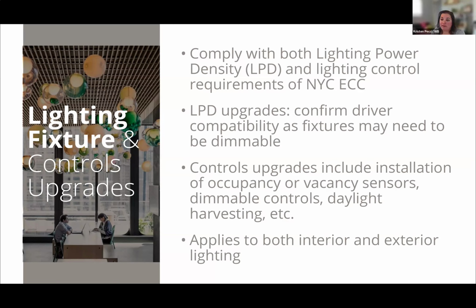The second part of the lighting upgrade requirements does factor into the control side, and this would include installation of automatic controls like occupancy or vacancy sensors, dimmable controls, daylight harvesting, and time-based controls, all of which are prescribed depending on the space type. So something like an open office area would require automatic controls, occupancy sensors, which would be automatic on, automatic off control. There are dimming requirements as well. Lighting fixtures located next to windows or under skylights have certain photocell requirements for daylight harvesting, etc. So depending on the space type or the architecture of the space, there are different controls requirements. And both sides of this, the lighting power densities and the control requirements, are applicable to both interior and exterior lighting.